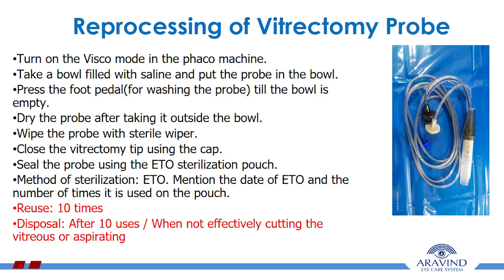Close the vitrectomy tip using the cap. Seal the probe using the ETO sterilization pouch. Method of sterilization is ETO. Also mention the date of ETO and the number of times it is used on the pouch. Reuse is 10 times and disposal after 10 uses or when not effectively cutting the vitreous or aspirating.